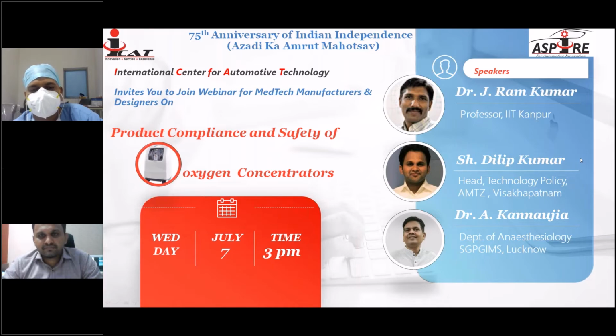So for VOC, lower flow at the highest possible temperature as far as the clinical scenario is considered, like 40 degrees or so. And for particulate matter, the highest possible flows, like if any oxygen concentrator is giving 5 liters, it should be tested at 5 liters maximum.